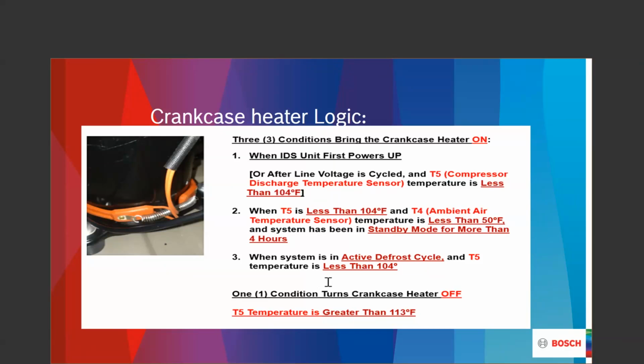So, a couple of things turn the crankcase heater on. You've got the T5 compressor discharge sensor. If it's less than 104 degrees, it's going to come on. If it's less than 104 degrees and the ambient temperature is less than 50, it's going to come on. Or if it's in the standby mode for 4 hours, it's going to come on, okay? If my system is in an active defrost cycle, so we're in the heat mode, we've been running and all of a sudden it goes into a defrost cycle, it will be turned on at that point in time also. And then it basically goes off when the T5, that's that sensor that's on the hot gas discharge line coming out of the compressor, reaches above 113.